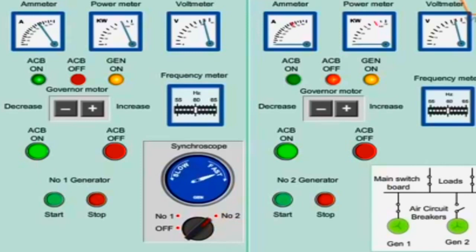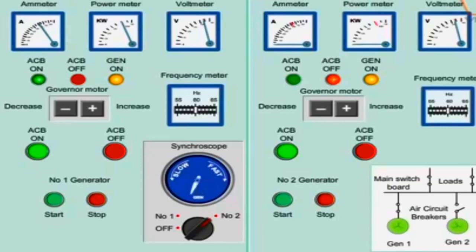If the needle rotates in a clockwise direction, the speed of the incoming generator should be decreased. If the needle rotates in an anti-clockwise direction, the speed of the incoming generator should be increased. The air circuit breaker should be closed when the incoming machine voltage is in phase with the bus bar voltage. It is advisable to close the breaker when the pointer rotates in the clockwise direction.